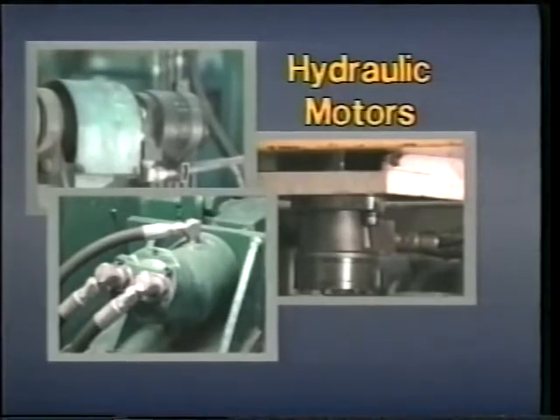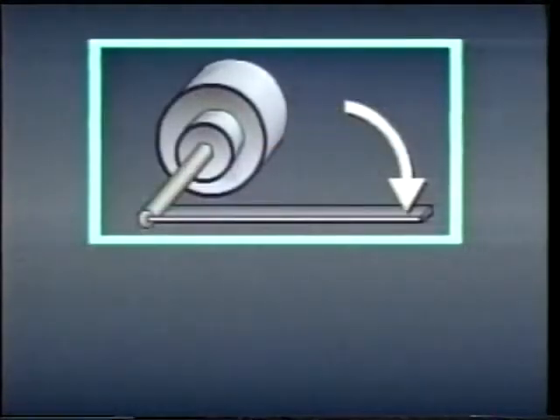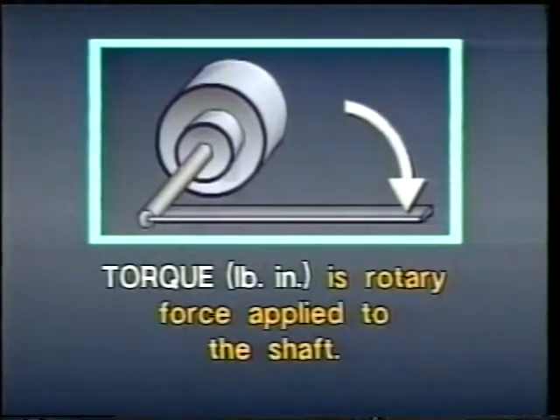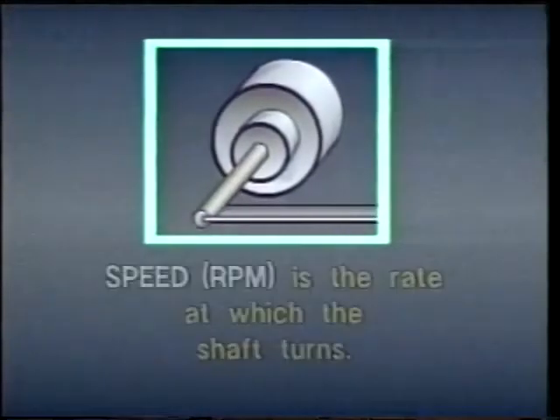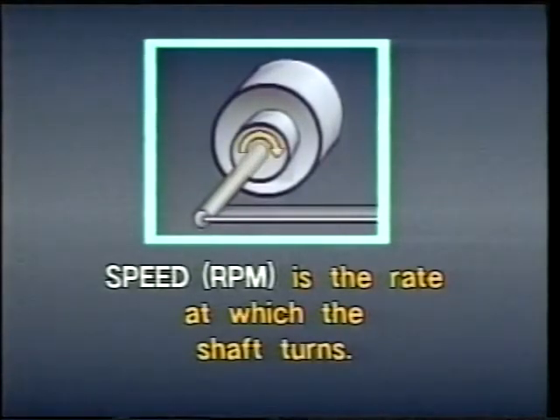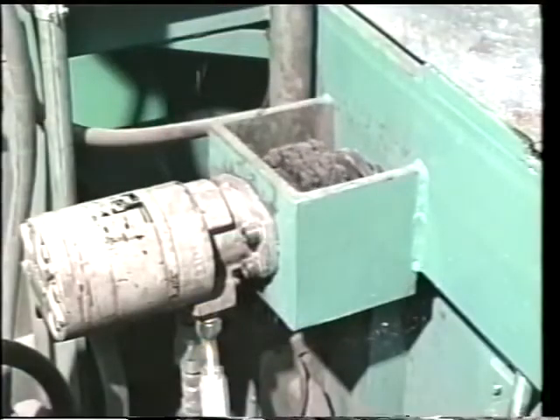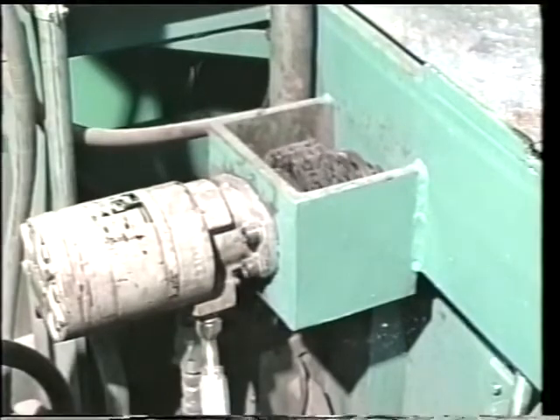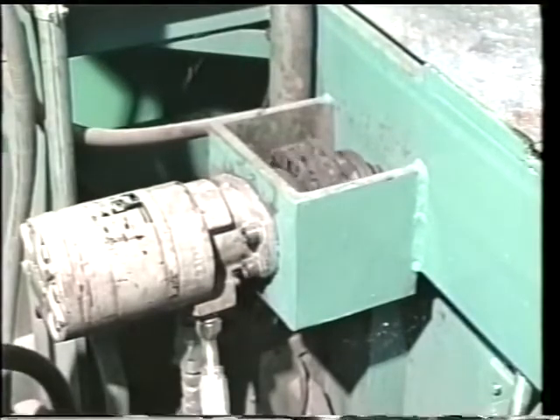When operating any motor, two main factors must be considered: torque and speed. Torque is the rotary force applied to the shaft, usually expressed in pound inches. Speed is the rate at which the shaft turns, usually expressed in revolutions per minute. Let's look at a vane motor to see how pressure and flow in a hydraulic system affect the motor's torque and speed.